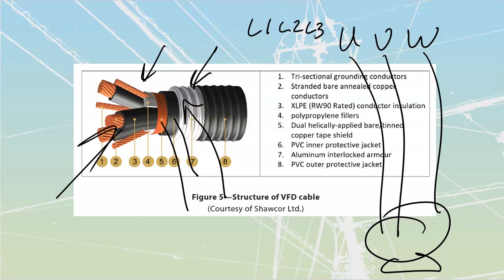You'll have installations where all the rest of the power wiring runs inside the cable tray, and then you'll have this single VFD cable strapped along the wall, because it's the only place you can do it where you won't cause interference.